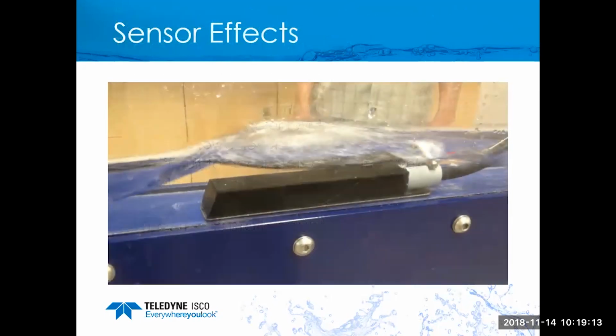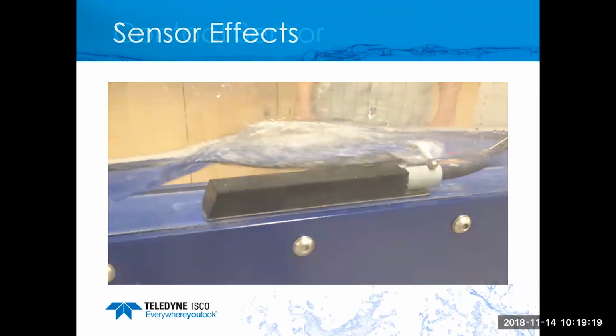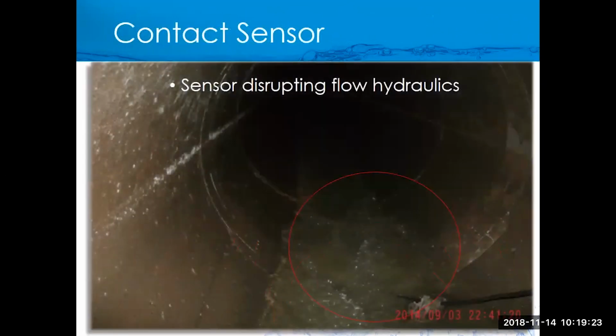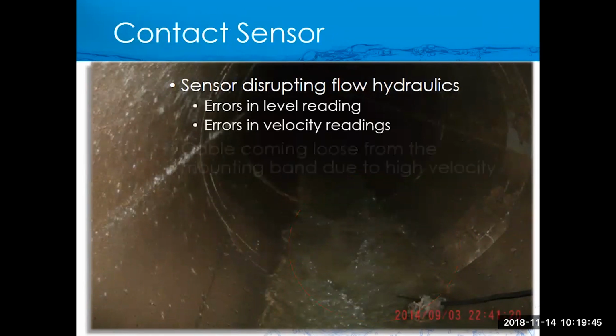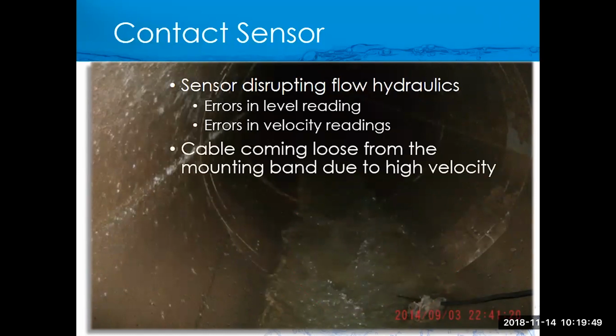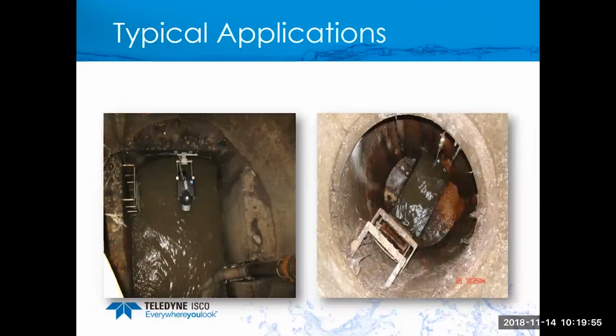Here's a picture I thought gave you a pretty good idea of just how a sensor will affect hydraulics, especially at a low level. Okay, here's another picture of a site where they had a standard AV sensor in there. You can see upstream the hydraulics look pretty good. As it got closer to the end of the pipe, we have a couple of things going on. We have a lot of turbulence due to something probably on that sensor, or it could be just the ring or the change in the pipe. In this case, we're going to have errors in our level reading, errors in velocity, and the cable is now coming loose from the band due to the high velocity coming at it. You can see it's already catching debris, so that's not a good thing. It's just not a good application for an in-pipe sensor.